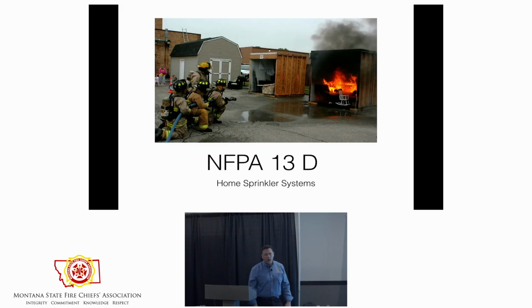Now, there's one more, and that's 13D. So this is what we put in homes. So in 13R, we omit attics. We omit combustible concealed spaces. There's no sprinklers in small bathrooms, no sprinklers in small closets. 10-minute water supply. That's it. Life safety, 13R. 13 is much more robust.